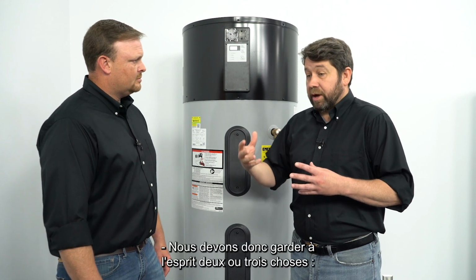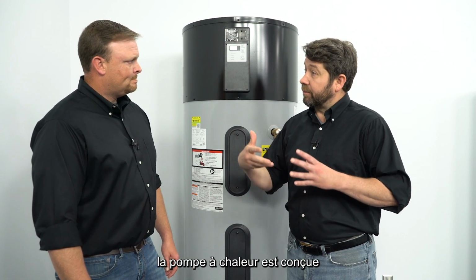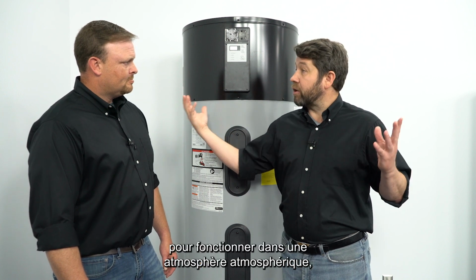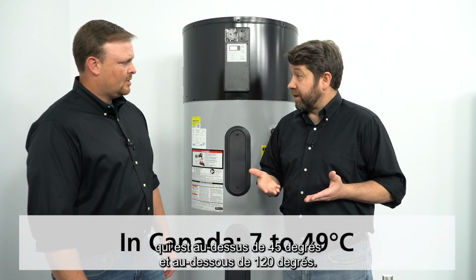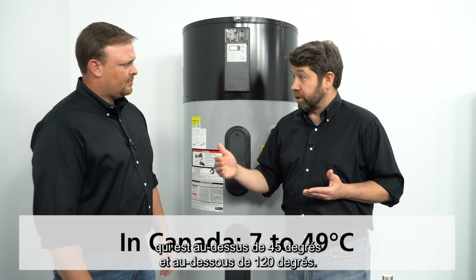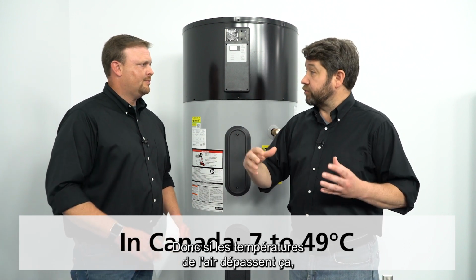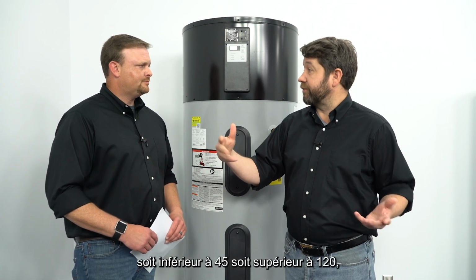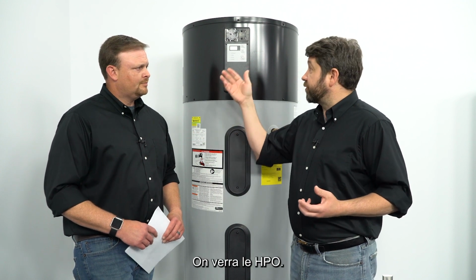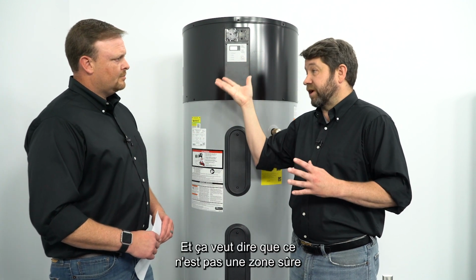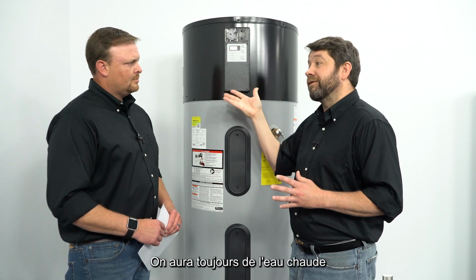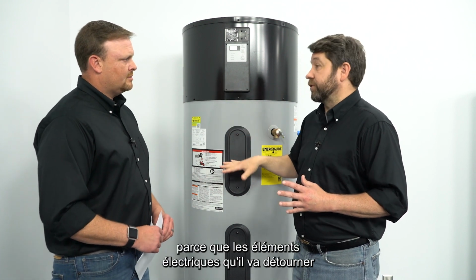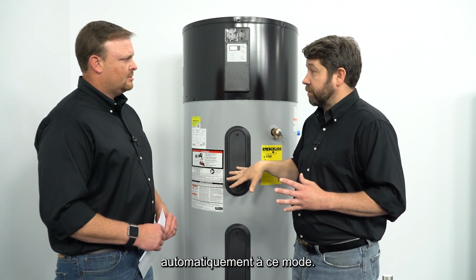A couple of things that we have to keep in mind. The heat pump is designed to work in an air atmosphere that is above 45 degrees and below 120 degrees. So if the air temperatures exceed that, either below 45 or above 120, we'll see the HPO displayed there. And what that means is it's not a safe range for the heat pump to work. We'll still have hot water because the electric elements, it's going to divert automatically to that mode.